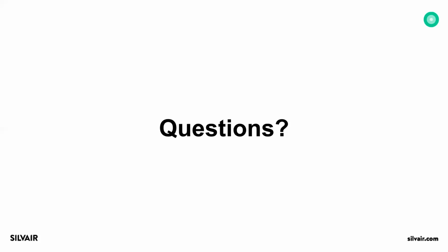We have also similar questions. I would like to check if this answer also covers those questions. So we have a project with several zones managed by a gateway. Can we still have one zone managed by in-node or on a separate schedule scenario? Yes, it is possible. Just those nodes need to be able to have 2.20 firmware, and they need to be updated and configured properly. So have a profile and in-node scheduling events.